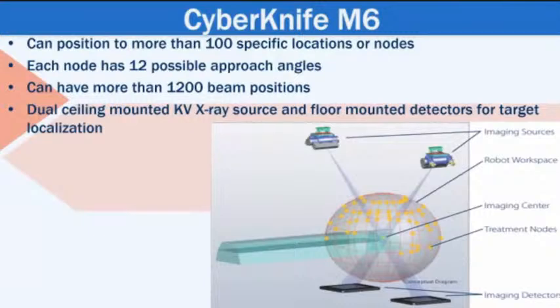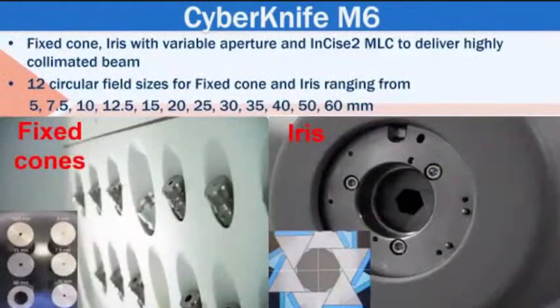During treatment, the image system automatically adjusts the robot position to ensure constant beam accuracy throughout treatment. The CyberKnife features 3 collimator housing types: fixed cone, iris with variable aperture, and the InCise2 multi-leaf collimator. There are 12 circular field sizes for fixed cone and iris. The field sizes range from 5 mm to 60 mm. The planner can choose the best collimator for the given treatment during the planning process.